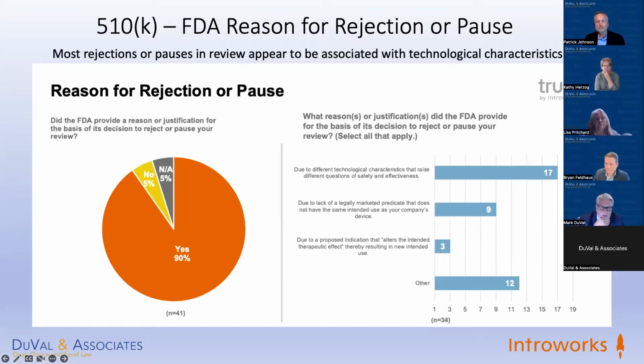And as Kathy noted, a lot of times we're having to debate the agency on these. And I think, Patrick, you mentioned the word evolution. We oftentimes try and present to the FDA, look, if you look at the evolution of the predicate family, the big jump, if there's any leap or difference in the technological characteristics, it might be in products or devices that preceded your submission. And then the FDA will tell you, well, you've got different technological characteristics. And we'll say, well, look, ours is very modest in comparison to the big jumps you made before us. And so in the span of this family, we really are not an outlier. And we often win on that argument at the submission level.